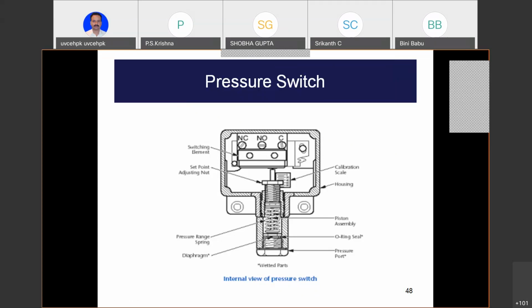I told you a topic which runs to 3 chapters in 15 seconds. I got the message: there are 3 types of failures. Failure safe, detected, and undetected. It suddenly tripped for no reason because the micro switch wire got loose. Safe. That micro switch is jammed and nobody knows. Danger. And double danger because you have not detected it. But today I'm walking past and I test it and I find it's in danger. It's luck. So that is danger but detected.